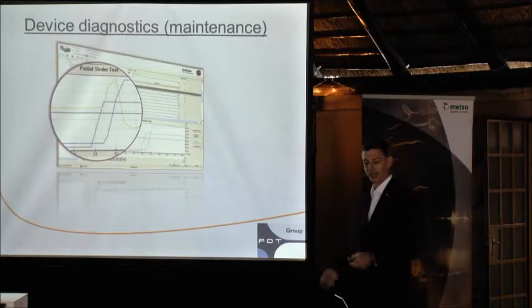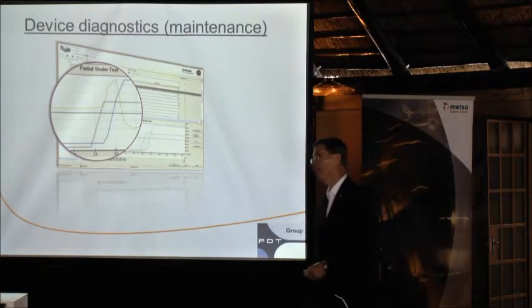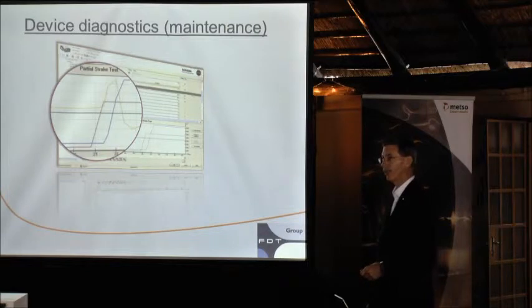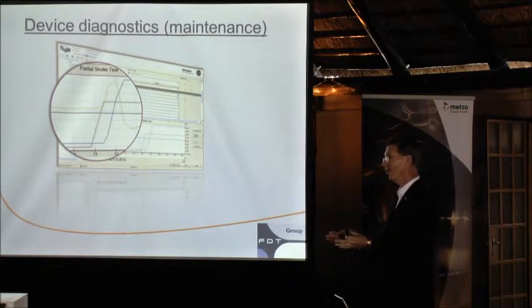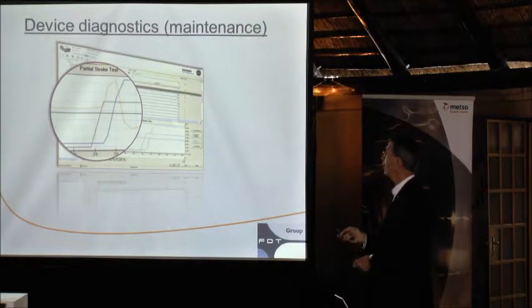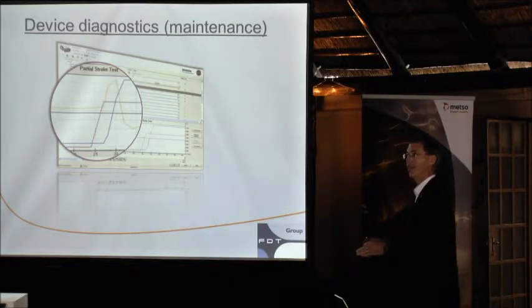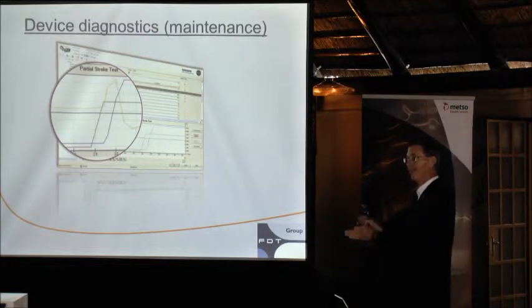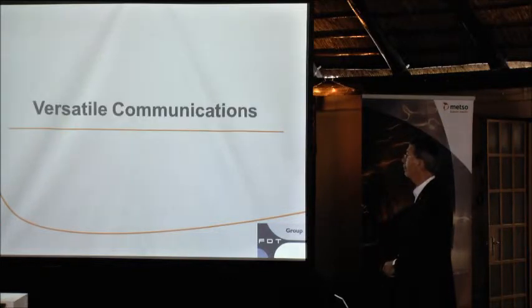One of the most complex preventive maintenance functions in most facilities is the partial stroke test. In the past, it was so complex that companies built entire tool environments around it so you could run PSTs within your DCS or PLC application, since it's a critical but hard to execute function. Now partial stroke tests are handled completely by the DTM itself, integrated directly by the valve controller or valve manufacturer into the driver that comes with the valve—no longer a separate app, but all integrated into the same platform.